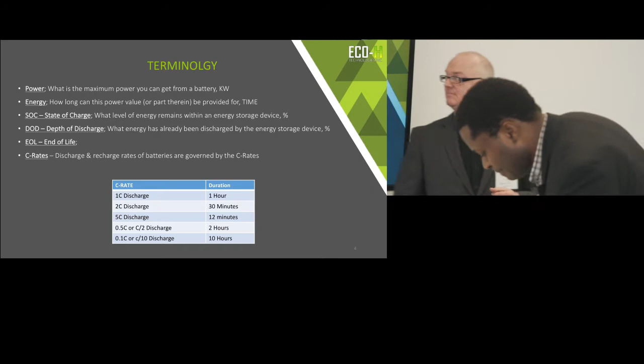So you've got 1 megawatt for 1 hour - that's a 1 megawatt hour system. But if you draw 500 kilowatts, you can then draw that for 2 hours. 250 kilowatts, you can do it for 4 hours, and so on and so forth. So it's a very simple linear relationship between power and energy.